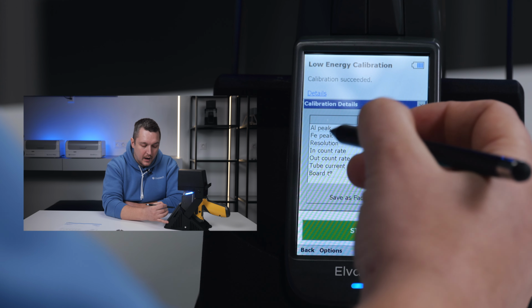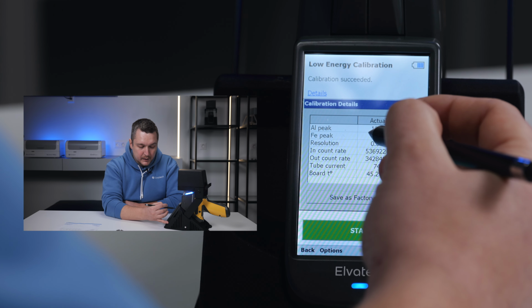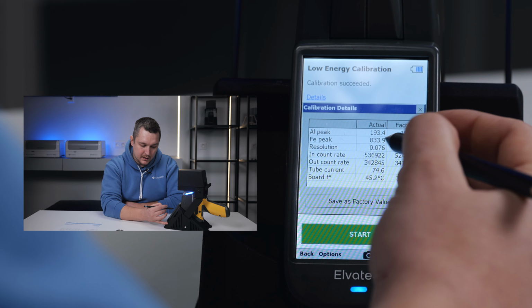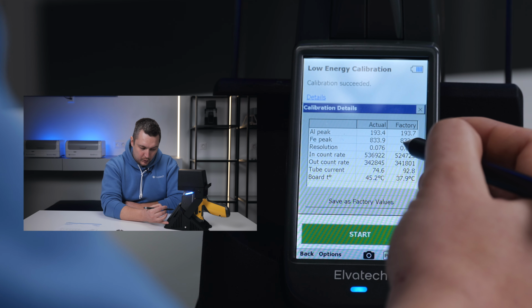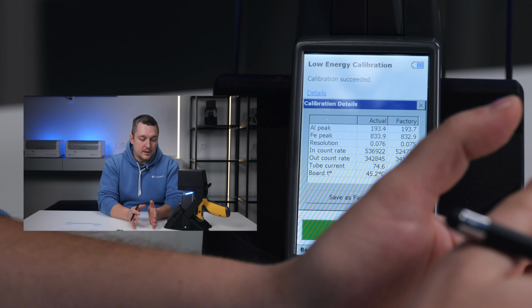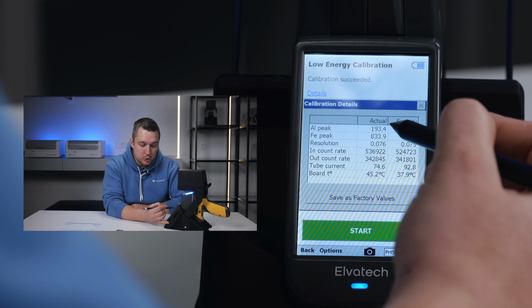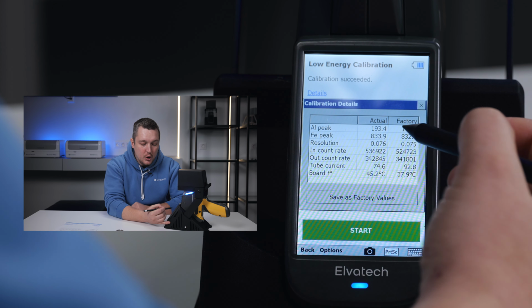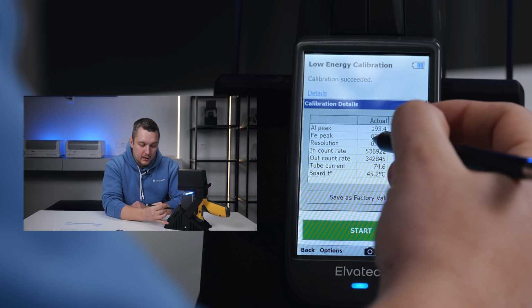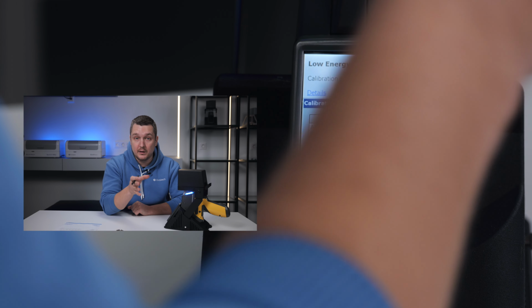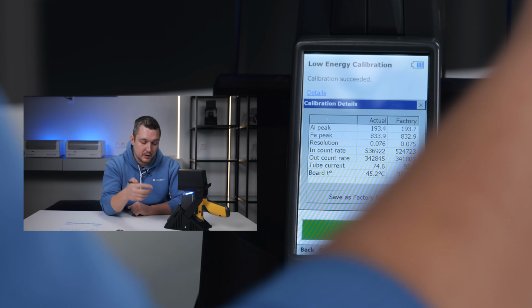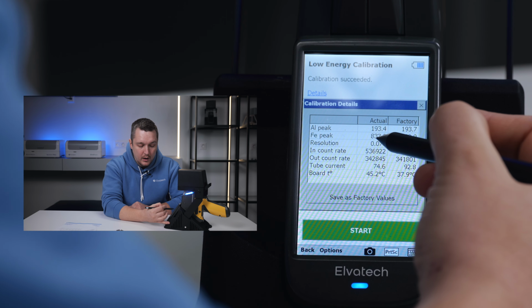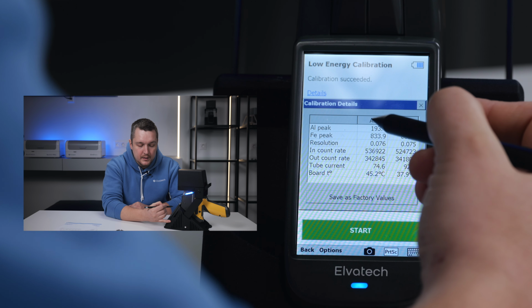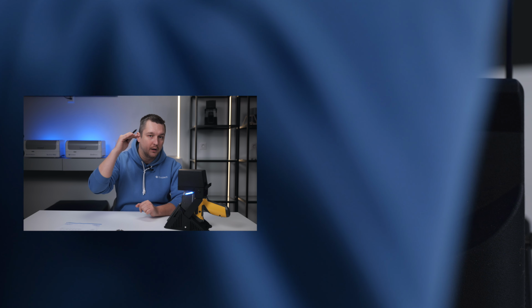And here we also need to compare the resolution of the detector. But here we have different numbers. The actual value is 0.076, and the factory was 0.075. Here the rule is almost the same, but the value of the resolution for light elements energy calibration should be no more than 0.090. So if you see here that you have 0.091, it's also the signal to contact our service department, so they will provide the remote diagnostic. But if you see here 0.076 as I have, or maybe 0.060, it is totally okay. It should be no more than 0.090.